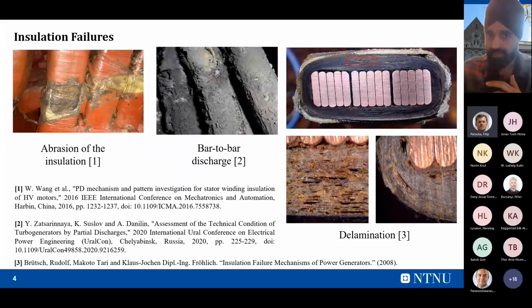Now, the expansion and contraction of these materials is different because they have different thermal coefficients. Due to that, there might be a chance of gaps forming inside the insulation or near the copper endpoints. This is our copper conductor, and near this point we have some gaps. These gaps are called delamination of the insulation.